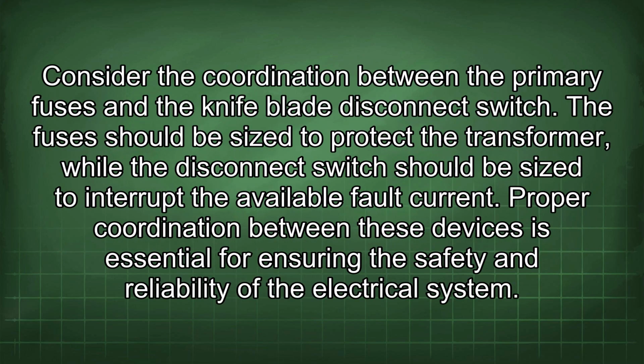Consider the coordination between the primary fuses and the knife blade disconnect switch. The fuses should be sized to protect the transformer, while the disconnect switch should be sized to interrupt the available fault current. Proper coordination between these devices is essential for ensuring the safety and reliability of the electrical system.